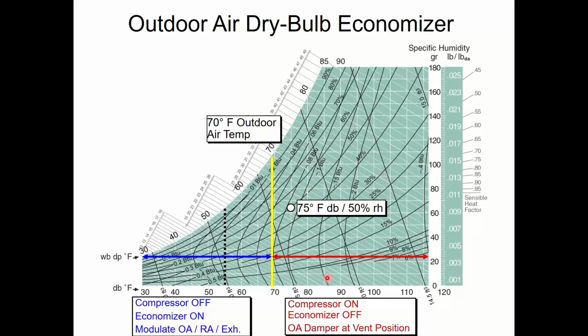So if I take the traditional 55-degree economizer set point that every technician has done for 40 years, this black line, everything to the left of that would be an economizer day, meaning do not use your compressor. Use the free cooling from outside, open the damper. Everything to the right would mean do not use the damper, run the compressor. Well, with the current code, that black line moves to this yellow spot. That means I have to take 60, 65, 68 degree air as my cooling days. That's okay. I probably can't cool your building with 68 degree air, but it's a good starting point, and maybe I run a compressor to supplement it, and I'll explain that in a second.